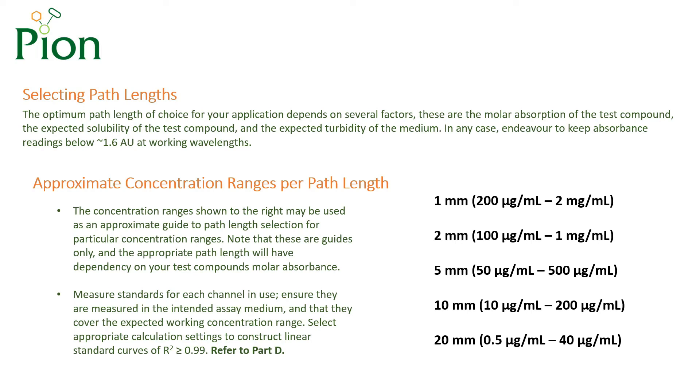When selecting a path length tip initially, we advise basing your initial selection on the expected concentration ranges shown here. Bear in mind that also you should aim to remain below a working absorption value of 1.6 absorbance units.